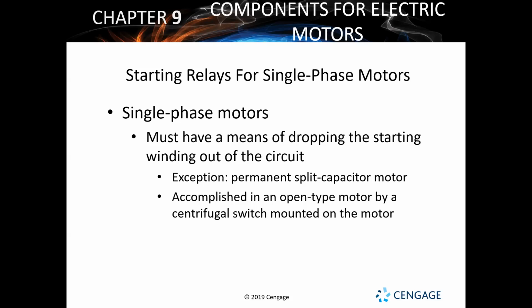When it first starts up, it needs a lot of energy. Once that energy is there, it'll move, and it can cut back the amount it needs to move, and it can just use the run windings on these single-phase split motors. So usually a capacitor is a really easy way to try and control that, depending on the motor. For a permanent split capacitor motor, that's the one exemption to this whole rule, though, because they have it where the capacitor will generate and reconnect the start windings when it needs more energy in order to keep the motor moving.